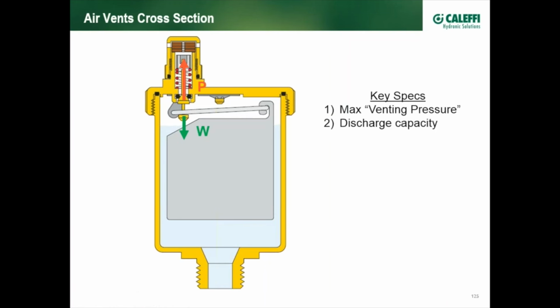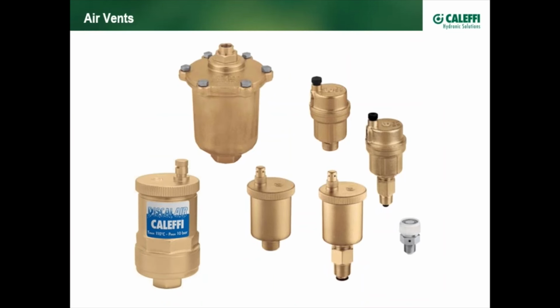The other key spec, discharge capacity. And that basically, as a function of a certain pressure, let's say 60 PSI, is how much the air vent is able to expel in terms of cubic feet per minute. And they're all rated differently. And obviously, the bigger valves are more highly rated.